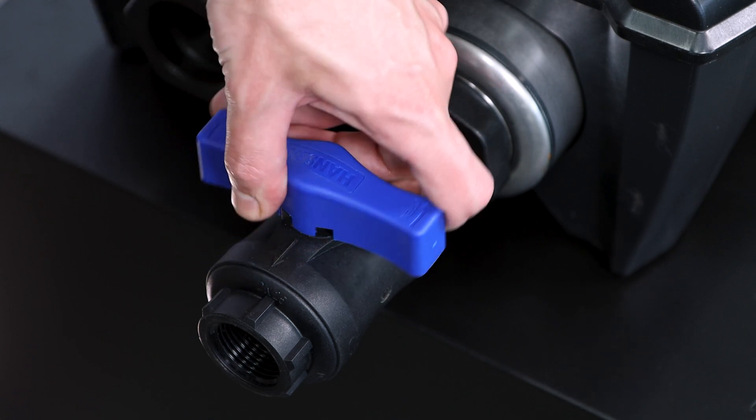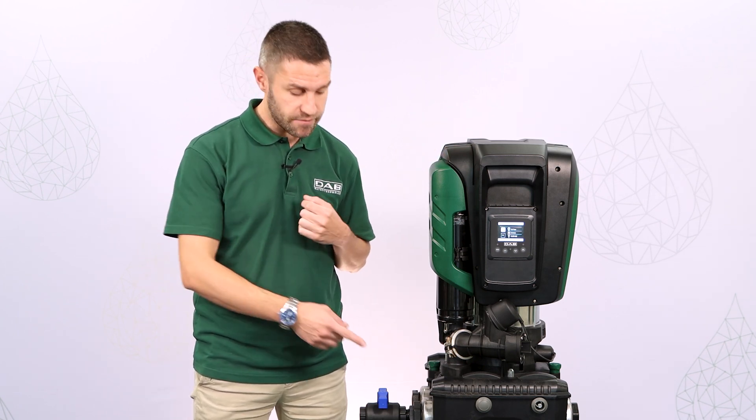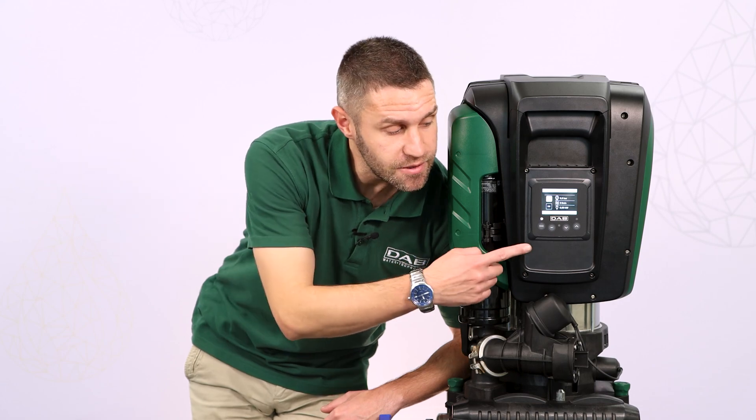We first need to determine if we have a leak in the pipeline. To begin, close the ball valve after the outlet of the pump. Observe the system's behavior. If the pump can't now retain the pressure, it means we have a leak in the pipeline. We are lucky enough that EasyBox Maxx displays the pressure value on the main screen without the need for an external pressure gauge.